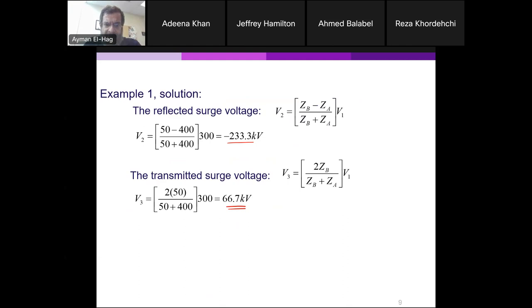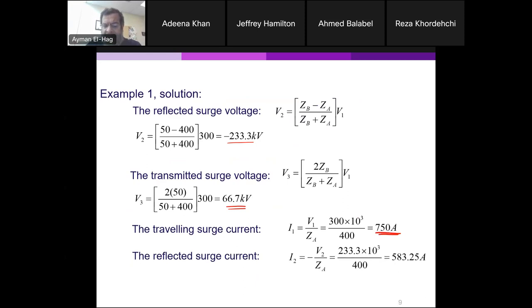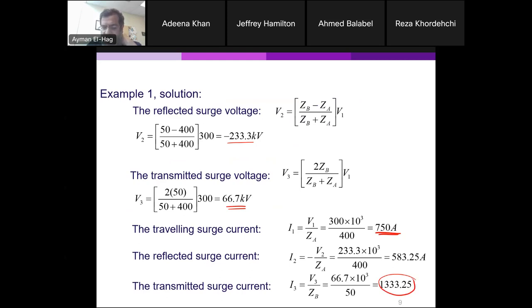So 300 kilovolt hit the line, minus 233 going back, 66.7 will make it to the other side. The traveling surge current, you divide this, this is V1 and this is ZA. This is how much current is traveling, okay? And this is how much current is reflected, and this is how much current is making it to the other side. So we have very high surge current.